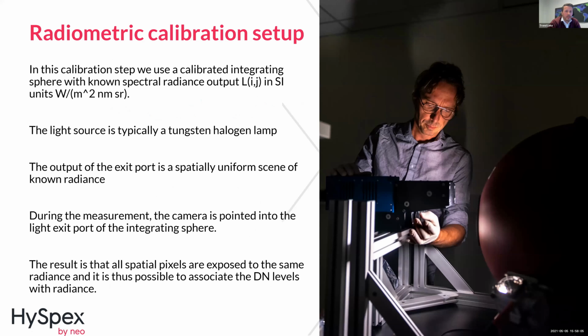Yeah, so the radiometric calibration setup is, as you see here on the right, we are looking into an integrating sphere with a known output radiance. And for us at least, the typical source is a tungsten halogen lamp. And the output is uniform. We know that because we have been around in Europe and the US and tested many integrating spheres, testing the uniformity. So the result is that every pixel is illuminated with the same amount of light, and then you can characterize your detector very accurately.